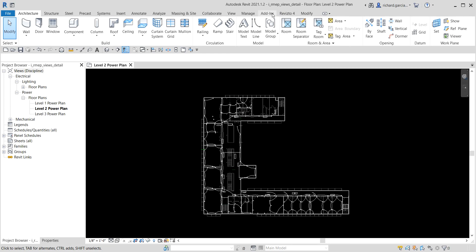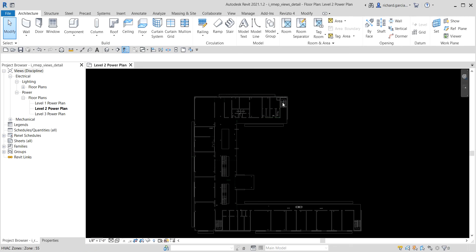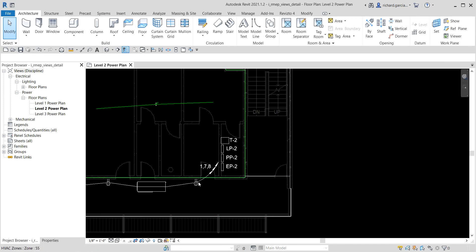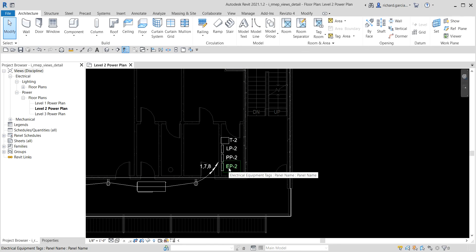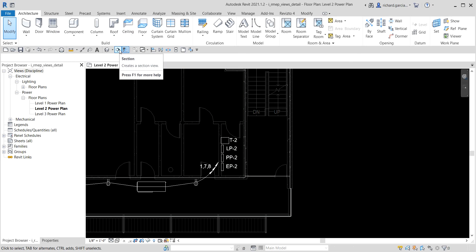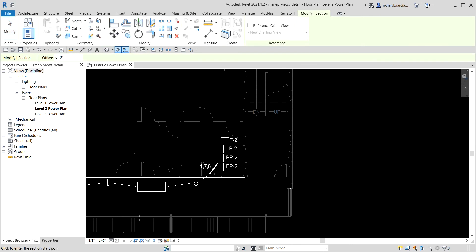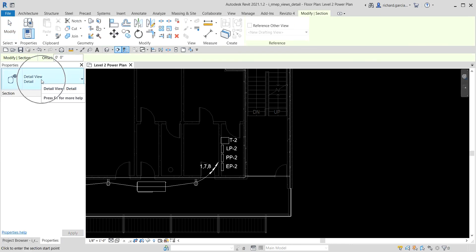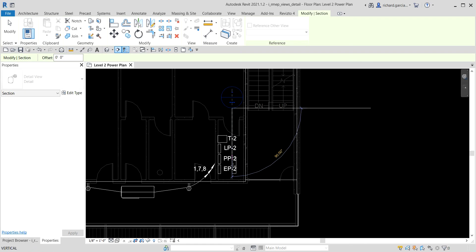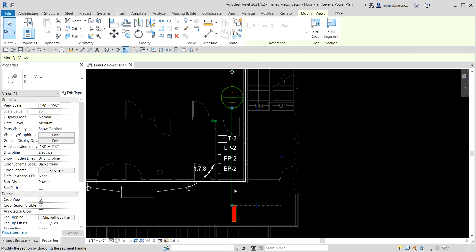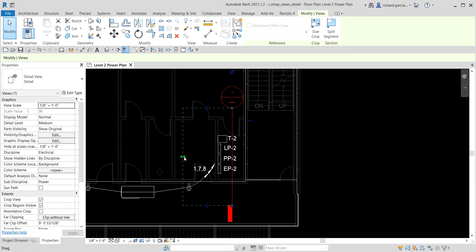I'm here on the Level 2 power plan. I'm going to create a section - zooming into the area I want to detail. From the quick access toolbar, I'll select the Section tool, check the properties to confirm the type is 'Detail View', then pick the start and end points. I'll flip the section to look to the left side and adjust the crop boundary.